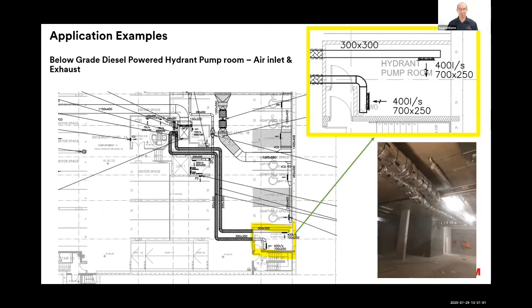This is an interesting one where a fire hydrant pump room was located below ground, so it's not possible to get air for driving the pump through the wall, and it had to be through ducting that entered a central shaft. So the pump room is the separated compartment, and the air to supply the pump so it could operate, and also the exhaust gases, had to be ducted through a car park, which is a separate compartment. And that was achieved by protecting the ductwork by wrapping the duct as it moves through the car park.